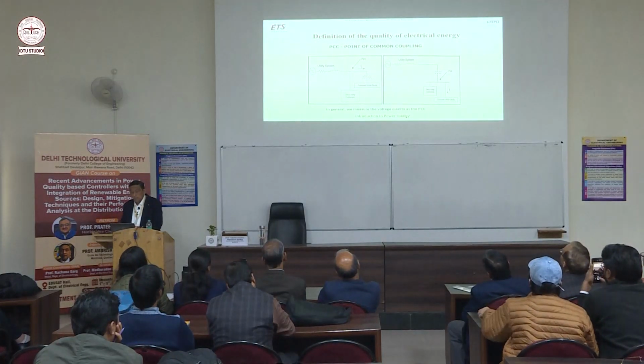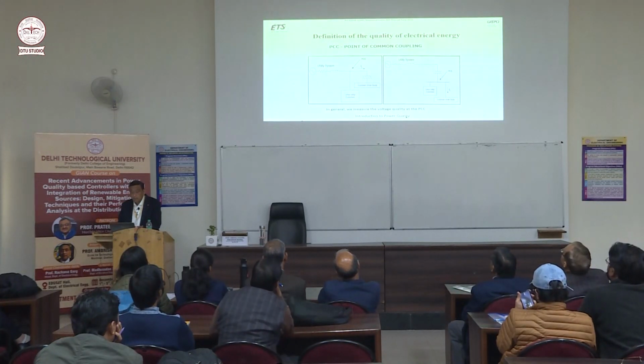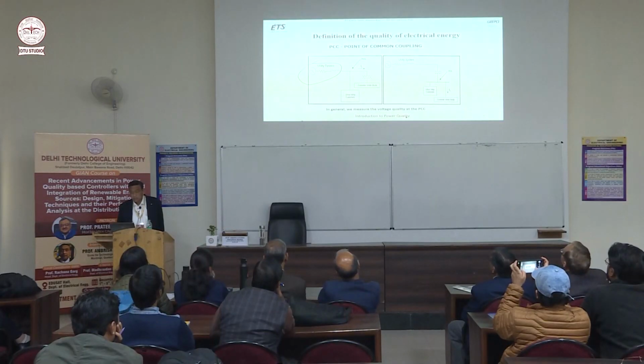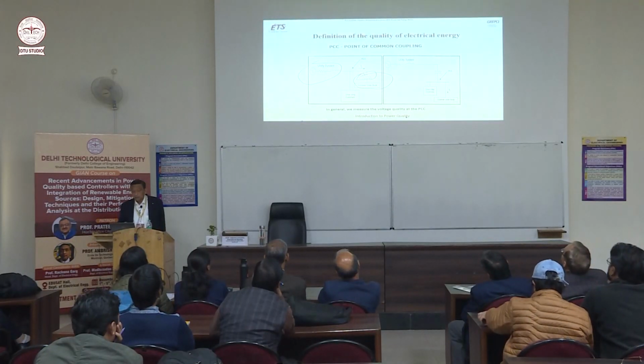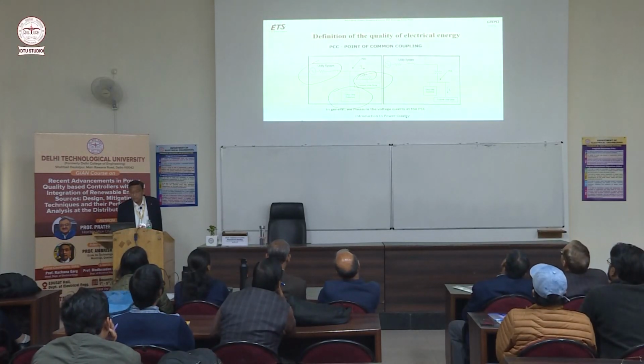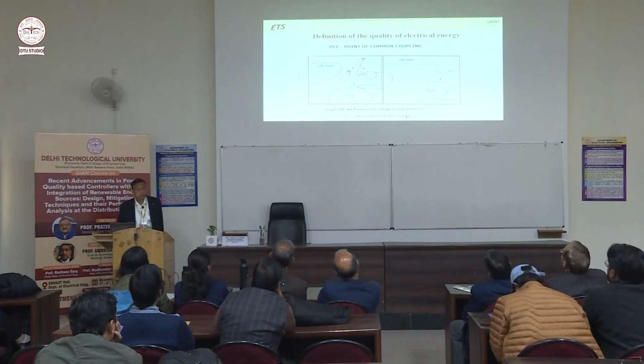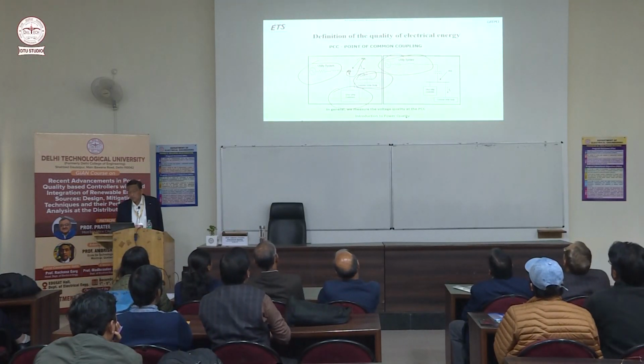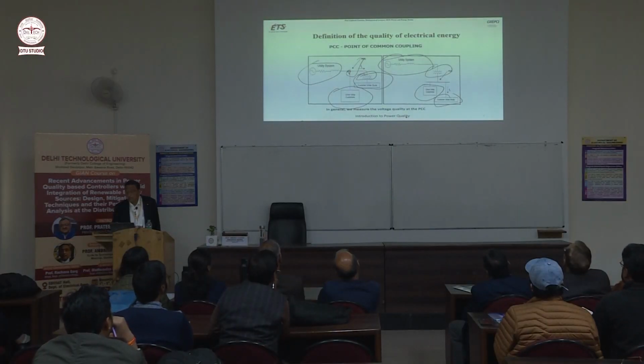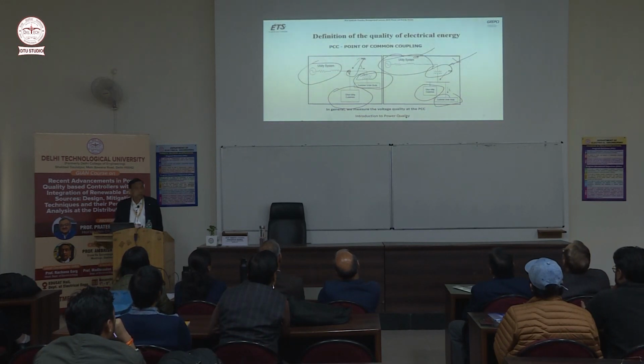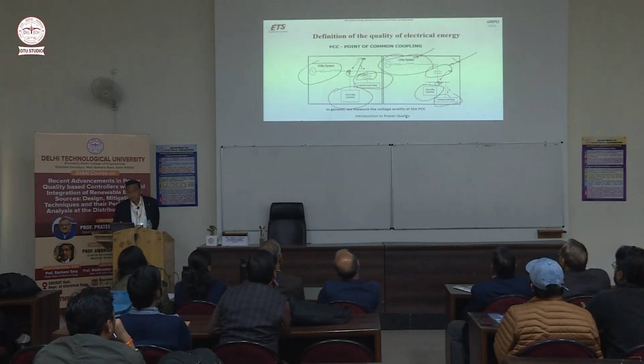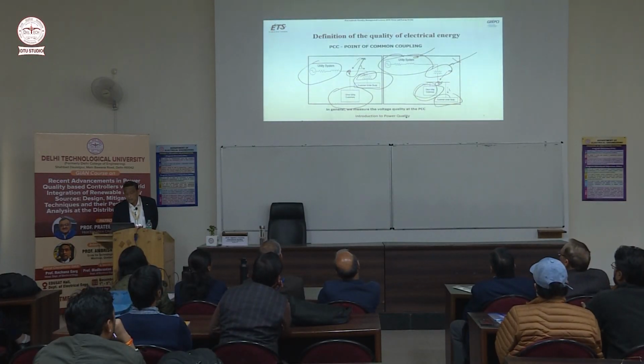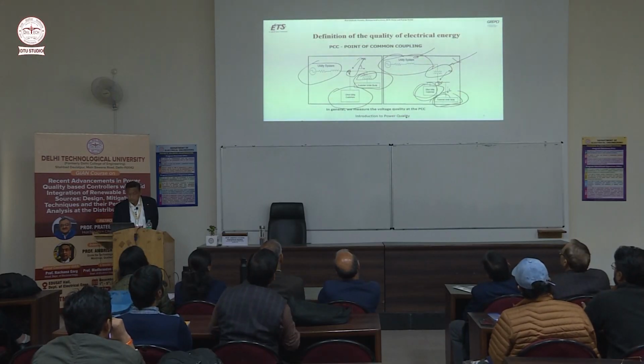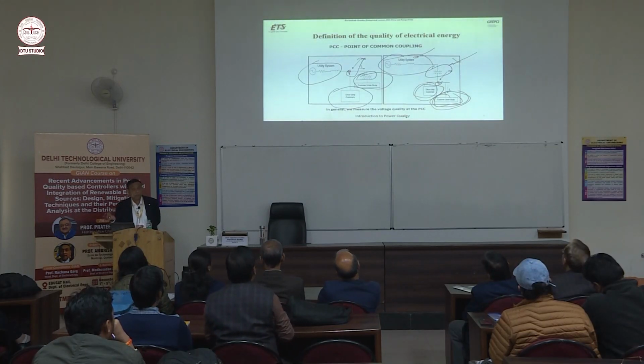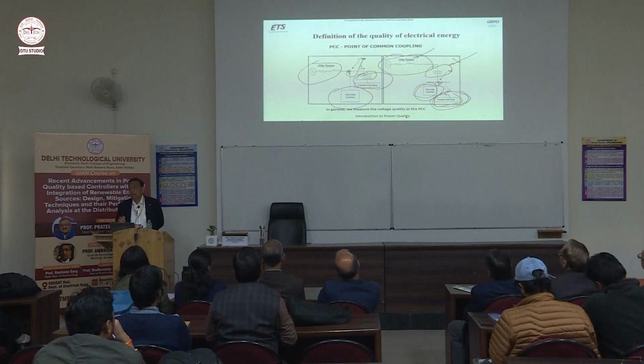As you can see, here is an example of PCC. This is the utility system, the supply system. Here is one customer, suppose under study, and this is the transformer of the customer, and there are other customers here. So this is the point of common coupling. But in this example, you can see this is the utility system and other customers, and this transformer is perhaps provided by the utility company, so PCC is here, where many customers are connected. If one customer is creating a problem, it will be reflected on the PCC, and the other customers will also get affected.